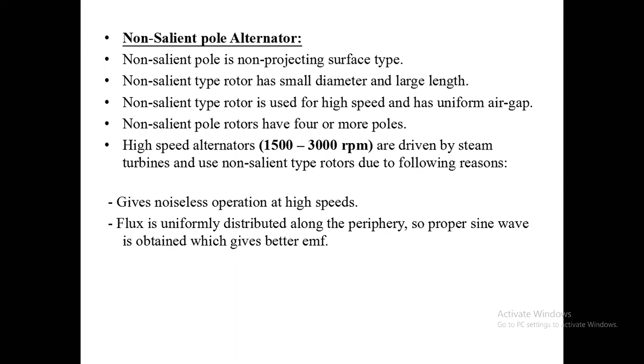Non-salient pole rotors have four or more poles, similar to the salient pole. High-speed alternators are driven by steam turbines and use non-salient type of rotors due to the following reasons. So they give noiseless operation at higher speeds. Flux is uniformly distributed along the periphery. Since we have a uniform air gap, obviously there will be a uniform distribution of the flux. So proper sine wave is obtained, which gives the better EMF.